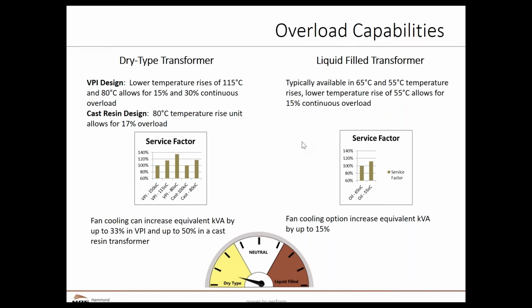As a result, depending on if it's a VPI design or a cast coil design, we can get somewhere between 15 and 30% additional continuous overcapacity with a dry type transformer. And if we add fan cooling, we can get between 33 and 50% additional capacity over the base nameplate. With liquid filled transformers, while they run cooler, they have less ability to do overload conditions. And typically the most common one would be 15% overload capacity. And fan cooling can give you an additional potential 15% additional capacity.